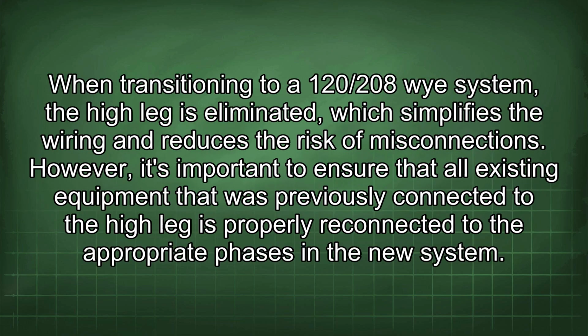When transitioning to a 120/208Y system, the high leg is eliminated, which simplifies the wiring and reduces the risk of misconnections. However, it's important to ensure that all existing equipment that was previously connected to the high leg is properly reconnected to the appropriate phases in the new system.